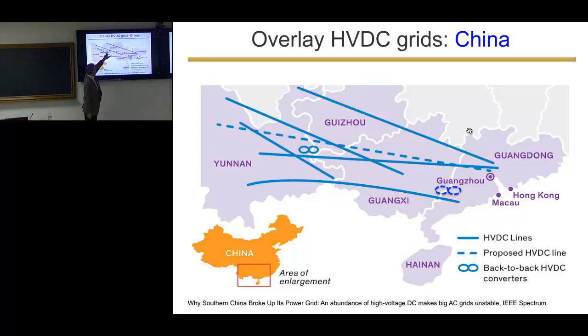Using back-to-back connections, so that this is no longer synchronous. What has so far been a synchronous area is being split into asynchronous areas linked with back-to-back converters, to prevent regional cascading in case of failure of the HVDC system. This problem was raised in IEEE: an abundance of high voltage DC makes big AC grids unstable, as discussed in Spectrum also - but you can't read the fonts from the back of the room.